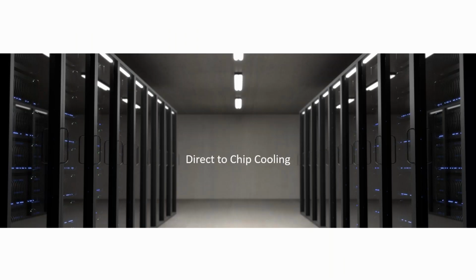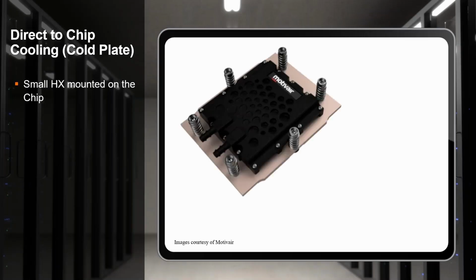Let's talk specifically about direct chip cooling. It's not the only technology that's being adopted, but it is being adopted at the highest rate of any type of liquid cooling. So here we're talking about liquid cold plates. We're bringing the water directly to the heat exchanger that sits on top of the servers, and we're pulling the heat away from the chips in that capacity.